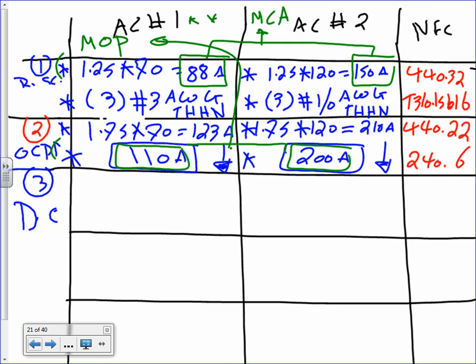Okay? If you don't have them, then you have to use the rated load amps and the full load amps and all the stuff. Do the calculation. This is minimum circuit ampacity. This is maximum overcurrent protection. There's chapter 12, guys, that talks about these terms. When we reach it, it talks about these. And we talked about them in one of the other projects for a single phase. Remember, this is really the only difference, it is three phase here.